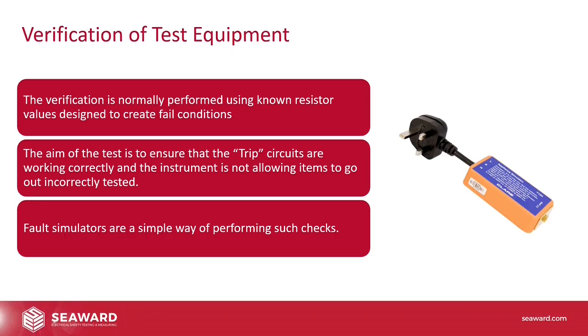Verifying the test equipment is really important too. It's normally done using a known resistor value designed to create a fail condition. The theory is that if you are using a tester, you want to make sure that that tester can correctly identify a fail condition. The way we do that is by using something like that Y160 on screen there. The idea is that the tester will trip if the circuits are working correctly and the instrument is not allowing items to go out incorrectly tested. So what will happen is you'll run a test. This thing will be designed to fail that test. The tester will say fail. It'll cut the power. That's great. That's verified that the tester is correctly identifying a fail condition. And these fault simulators are a really simple way of performing these checks, and you can keep a record of these checks. We recommend doing this daily, but it might be that you do it twice daily, or it's entirely up to you.